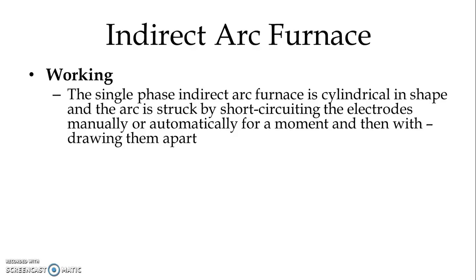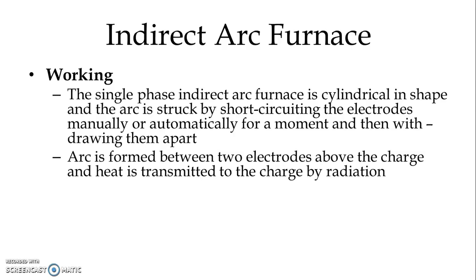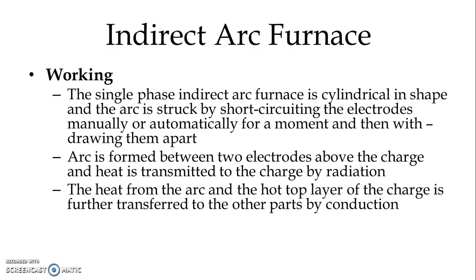The arc is struck by short-circuiting the electrodes manually or automatically for a moment and then withdrawing them apart. The arc is formed between two electrodes above the charge and heat is transmitted to the charge by way of radiation. The heat from the arc and the hot top layer of the charge is further transferred to other parts by way of conduction.